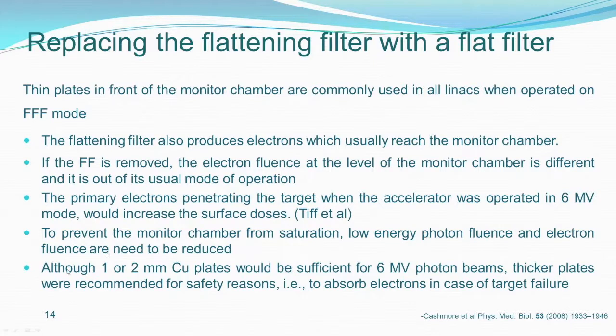It is normally recommended to have a 1 to 2 mm copper plate as a thin filter, but they actually use a much thicker plate. You know the reason. The reason is very interesting: to absorb electrons in case of target failure. Suppose the target fails. Earlier, your flattening filter was there to attenuate the electrons. But now if your target fails, the electrons will come straight down to the chamber and then to the patient. So a thicker plate will absorb those electrons in case of target failure.